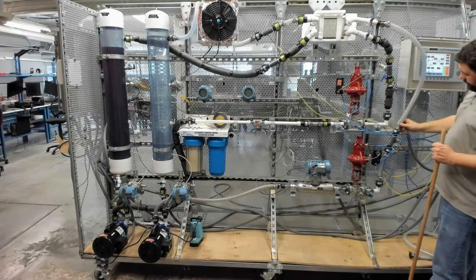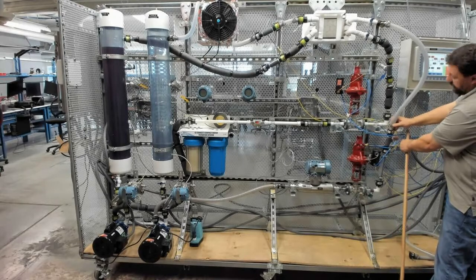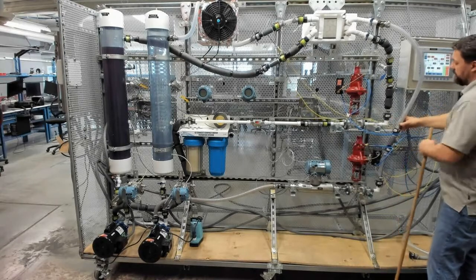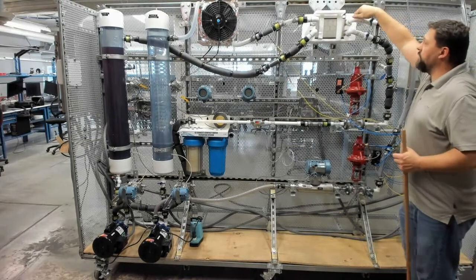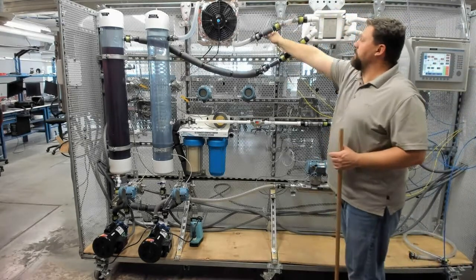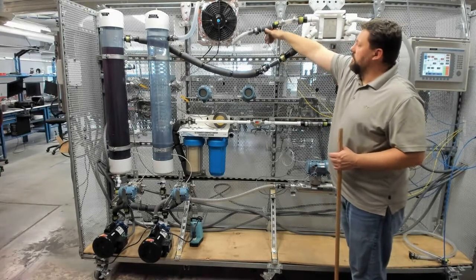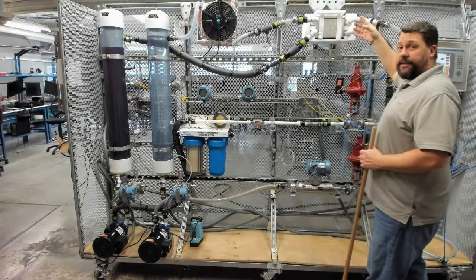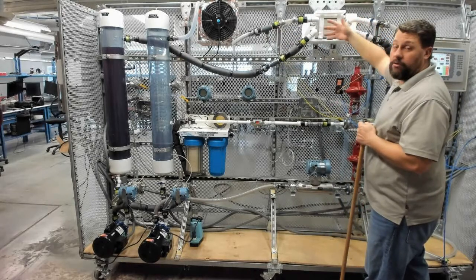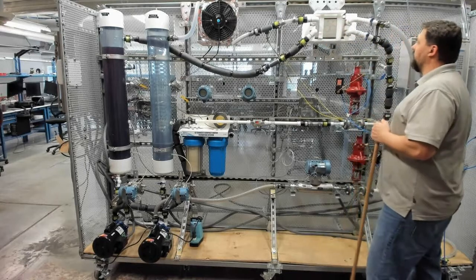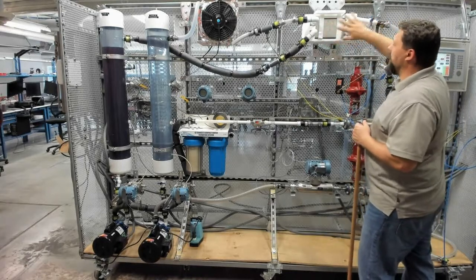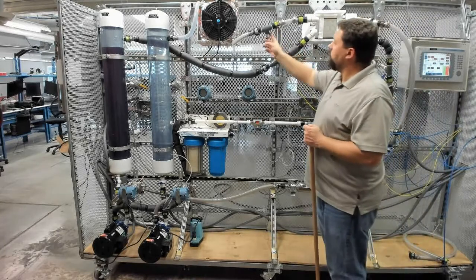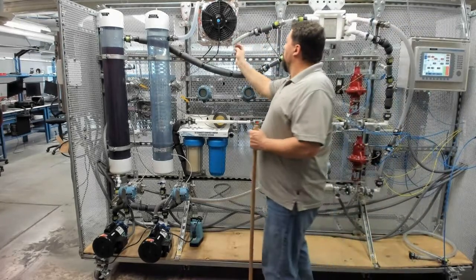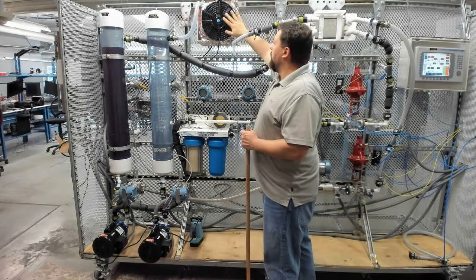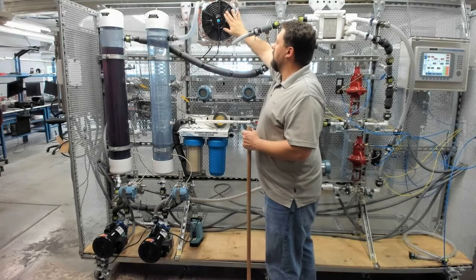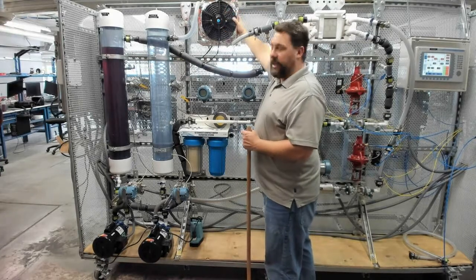The inlet temperature device is right here, so we're monitoring the inlet temperature of the heat exchanger, and then we come out of the heat exchanger right here to this other temperature element. Now right now it's configured for parallel flow. I'll get into what parallel flow is a little bit further along the way, but this is right now configured into parallel flow. And then these two fans here, there's one on the back here, one on this side, are for heat extraction.